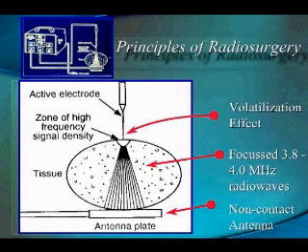active one. A thin wire tungsten electrode acts as the active part, and an insulated ground plate as the passive one. The passage of high-frequency radio waves heats up the tissues due to the natural resistance of the tissues to radio signals. The destruction and volatilization of the cells at the tip of the electrode is the result of the resistance and the heat produced, leaving behind a trail of dehydrated cells with consequent production of an incision.